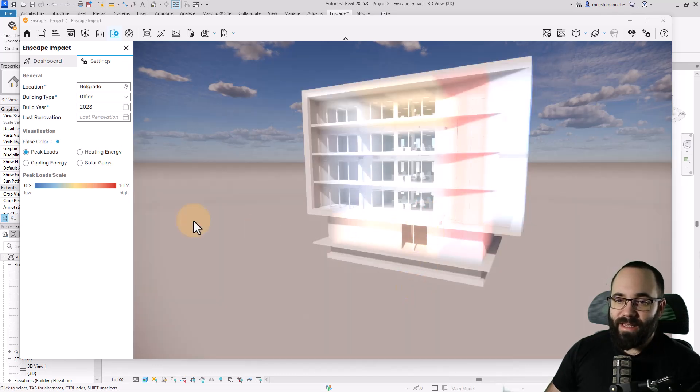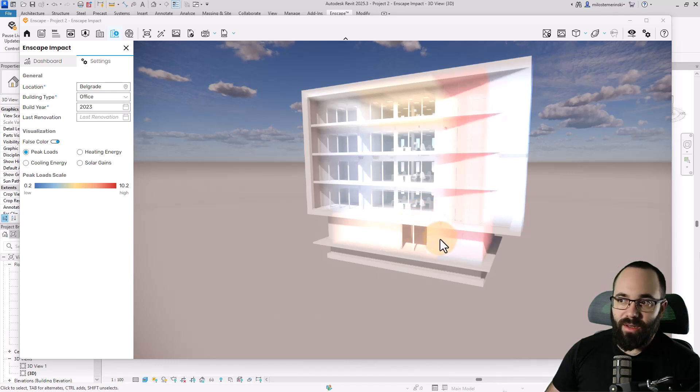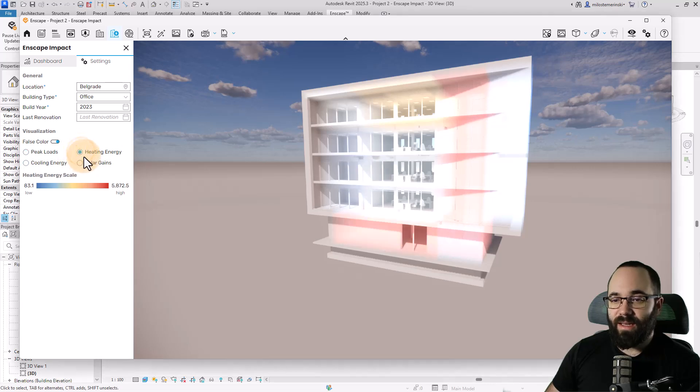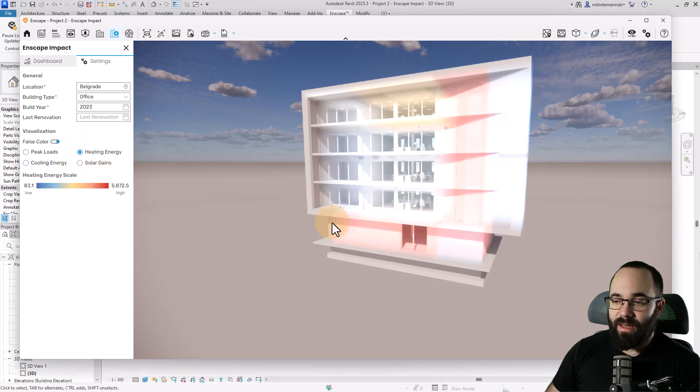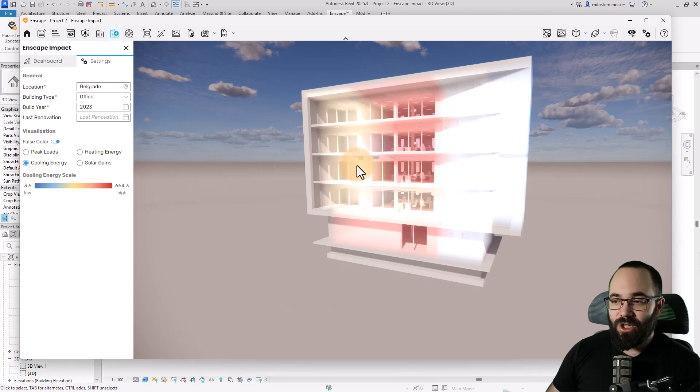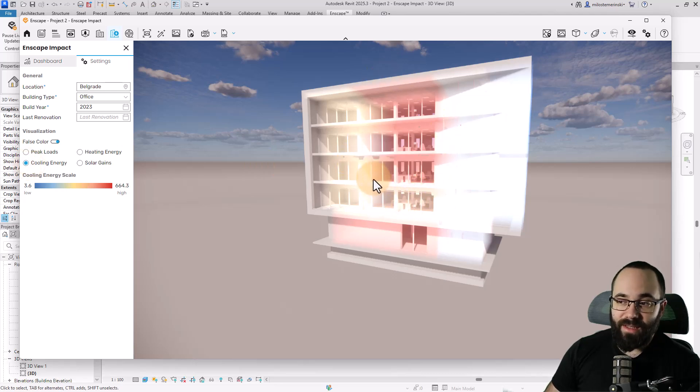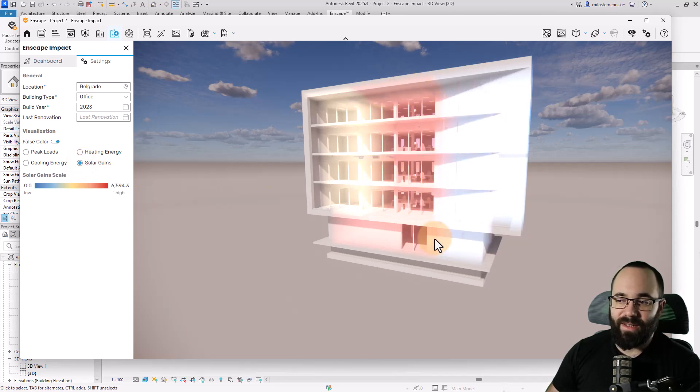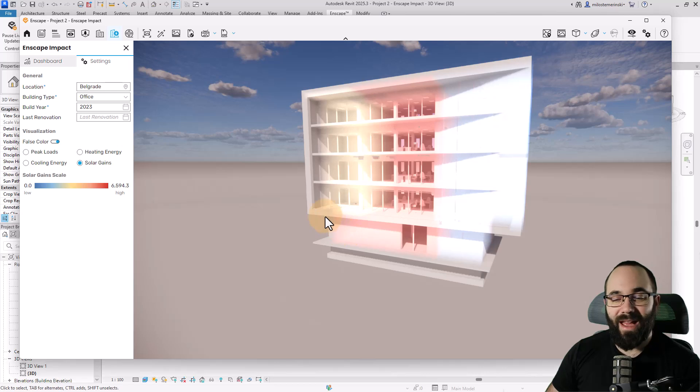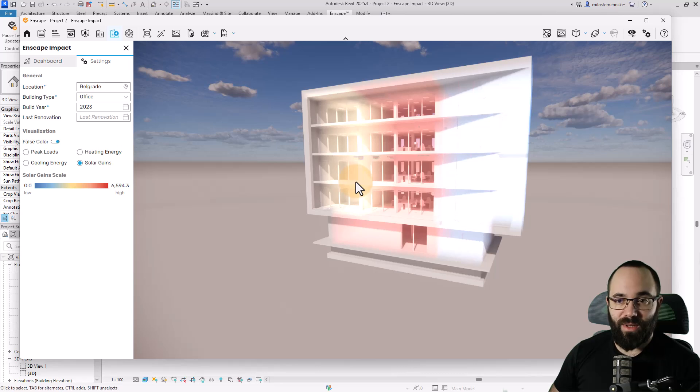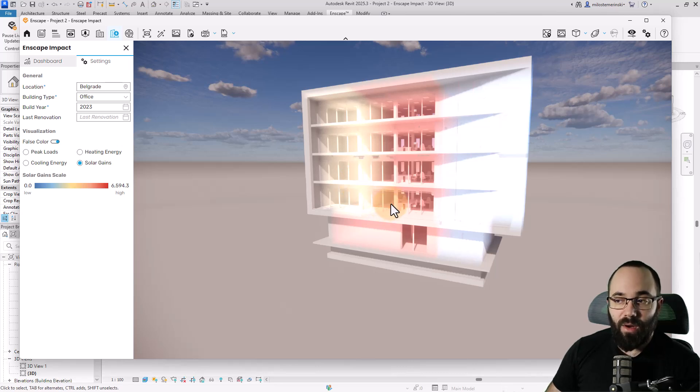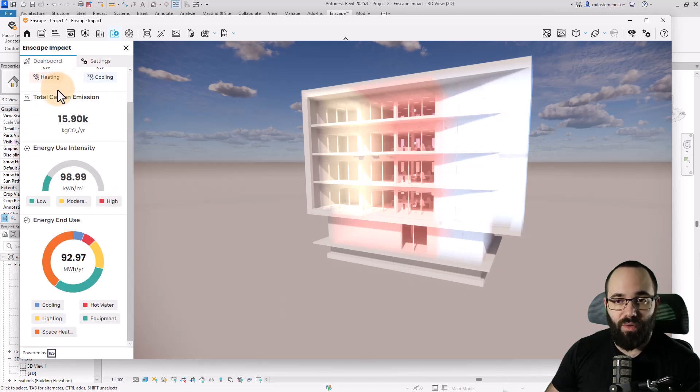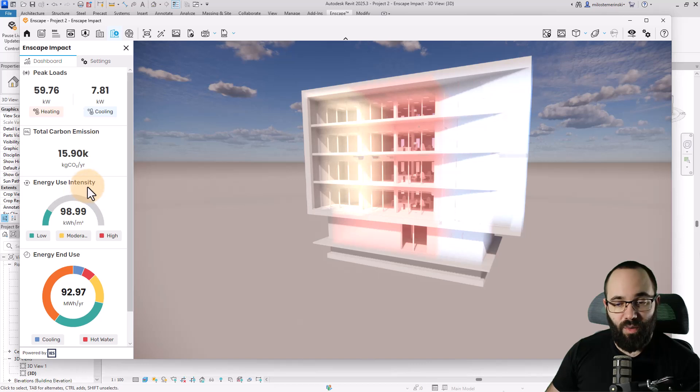Here we can obviously see that for peak loads, the trouble parts are this side of the building. We can also see the heating energy covers the bottom part of the building as well as this vertical part. For cooling energy, this is the most problematic spot, probably because it's an open space office with lots of windows. And for solar gains, it's covering the same area. So here we have that graphical info in 3D, which is what I really like. We know we should now focus on this part of the building if we want to improve the data displayed on our dashboard.